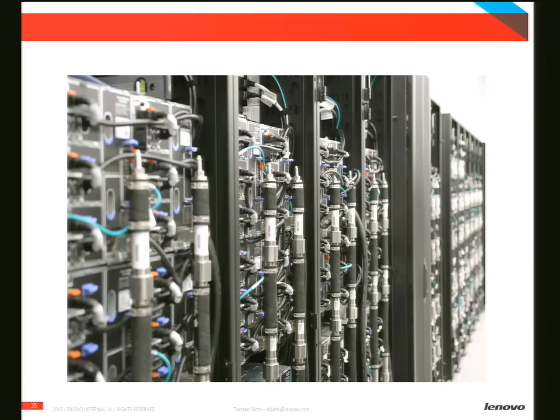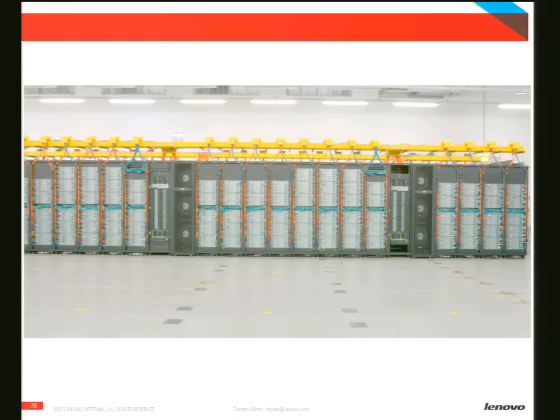The reason for stainless steel is simple, because of the microchannel cooler that we use. We can't use black steel in a normal data center environment, because you get corrosion, you get particles in the water and so forth. And we need stainless steel. So with stainless steel, we can achieve this efficient water cooling with really just 15 to 20 Kelvin delta T between junction temperature and inlet temperature. That's not sharp, the picture, but the current installation is running right now.